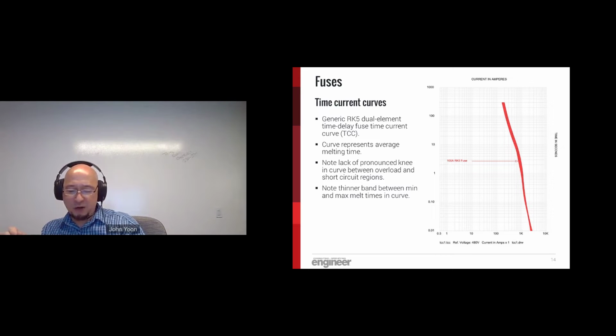Based on what we've seen so far, you should be getting the impression that these overcurrent protection devices will react very differently depending on how much current they see, whether it's a minor overload or a bolted fault on the other side of the spectrum. To be able to compare two different types of overcurrent protection devices, we use something that's called a time current curve. All manufacturers have these and they are of a similar format, so you can make easier comparisons between two different devices. If you look closely at this graph, you notice that the scales aren't linear. This is a log-log graph. So our per unit values go from 0.1 to 1 to 10 to 100 and so forth.